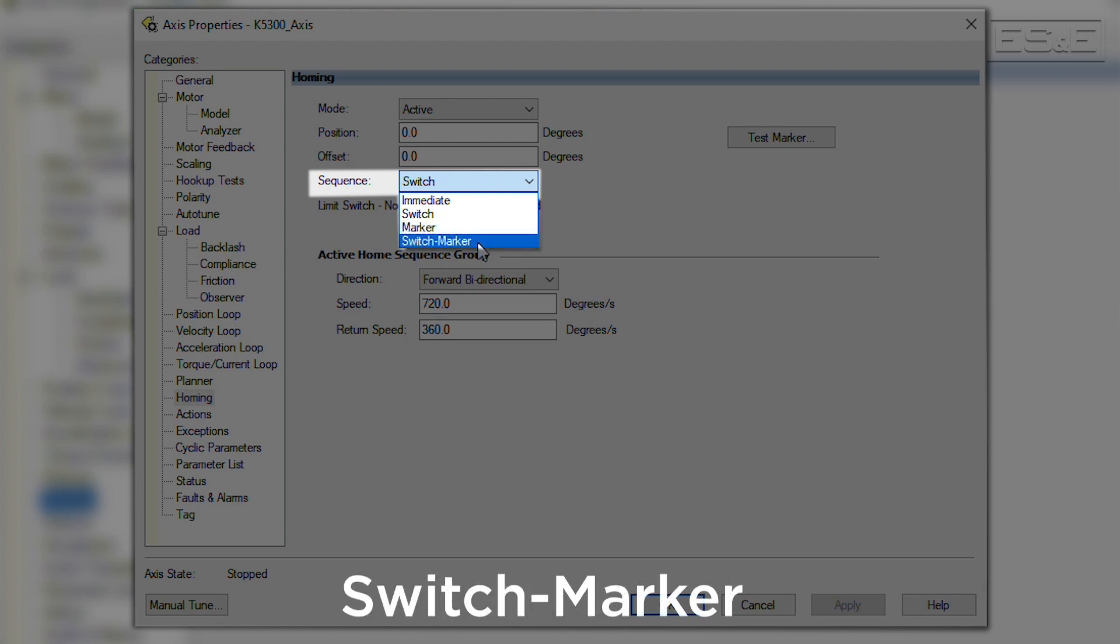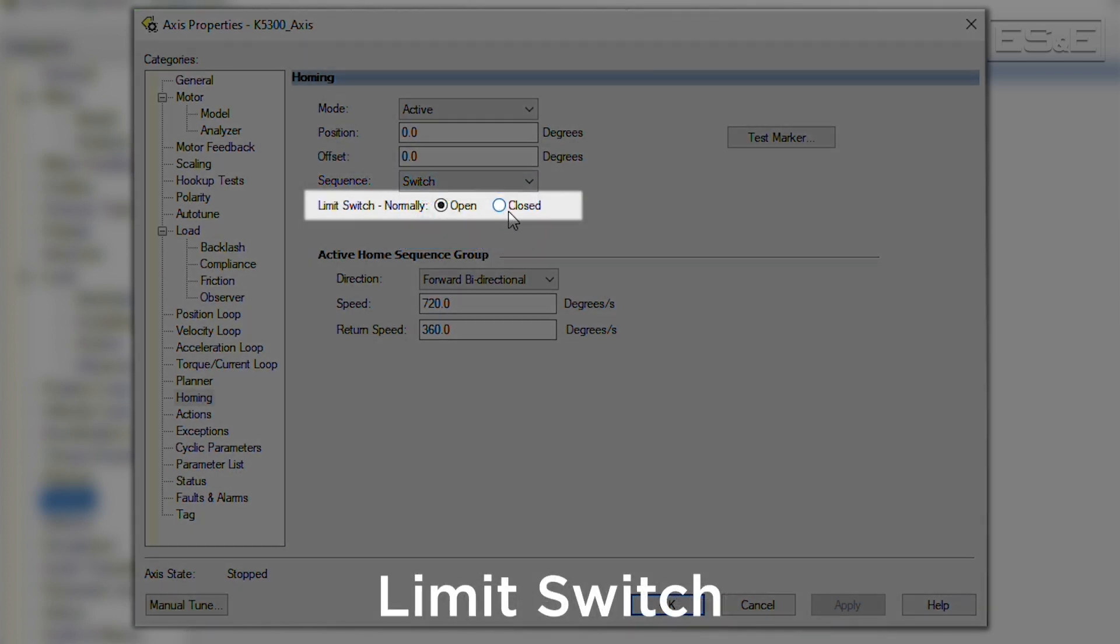If switch dash marker is selected, then the axis will need to move to the home switch and then continue moving until the marker pulse is detected. Using the marker pulse for homing is very accurate and should be used in applications that require finely tuned positioning. Finally, the limit switch selection defines if the home switch is normally open or normally closed.